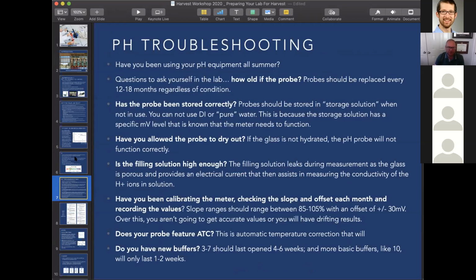So I put in some troubleshooting here in just two forms. I've got a graphical form, and then I've got some things to look at here for when I share the slides. But ask yourself when you're in the lab about pH, how old is the probe? The probe should be replaced every year to 18 months, regardless of condition. Has the probe been stored correctly? Probes should be stored in a storage solution. You can't use DI water to store it, and that's because, like I said, the storage solution has a very specific millivolt level that is known to the meter that needs that to function.